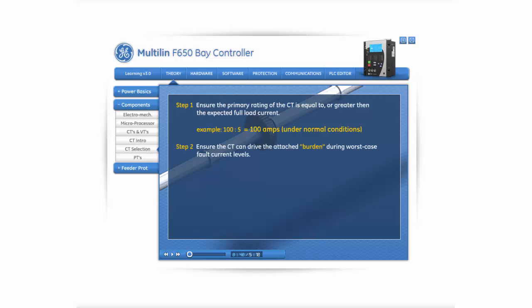The second step is to ensure that the CT can drive what is called the attached burden at the worst-case fault current levels without saturating. The burden refers to the total load resistance of the secondary circuit. The calculation for the burden is CT secondary resistance, which is the amount of resistance on the secondary windings of the CT, added to the connection wire resistance, which is supplied by the manufacturer, added to the relay's burden resistance, which is the resistance within the protection relay.